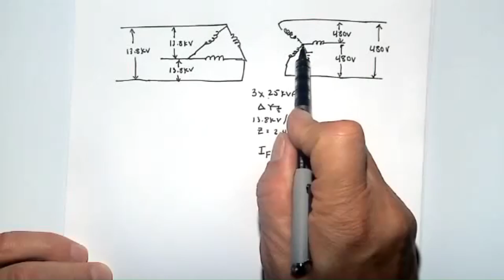So our difference in our calculation really is we're going to take this 3 times 25 kVA and make it a 75 kVA transformer. There's our square root of 3 and 13.8 kV. That works out to be about 3 amps. So again, even though the wire size could be very, very small, in this case, we only need about 3 amps on the primary. And on the secondary, again, we already know what that's going to be. It's going to be 75 times 1.2, or about 90 amps. So again, we're starting to become more and more comfortable with that. Why is that? Because we're a 480 volt system. Our multiplier on our kVA is about 1.2, so we're at about 90 amps.